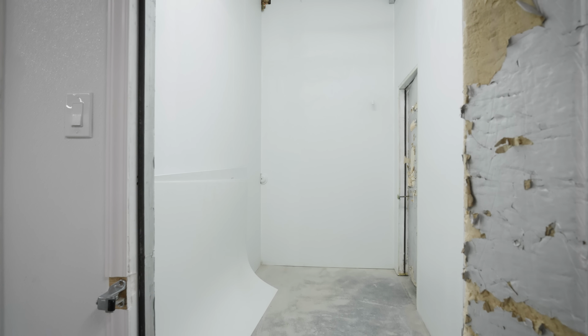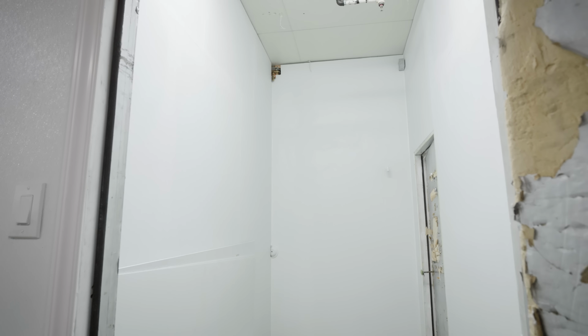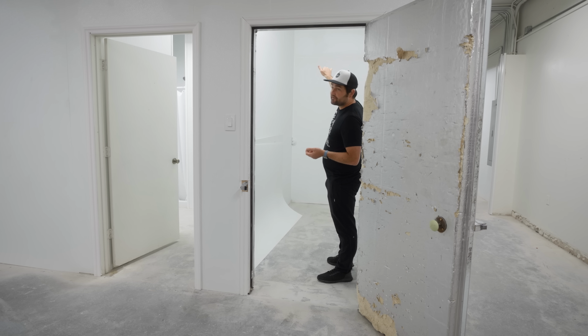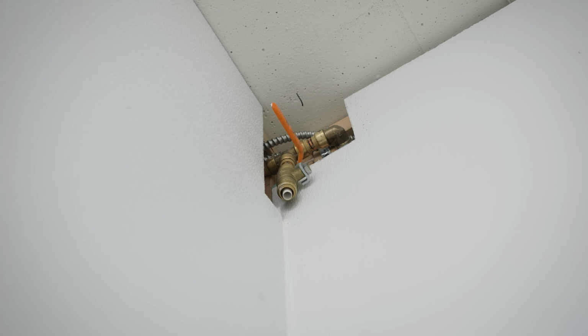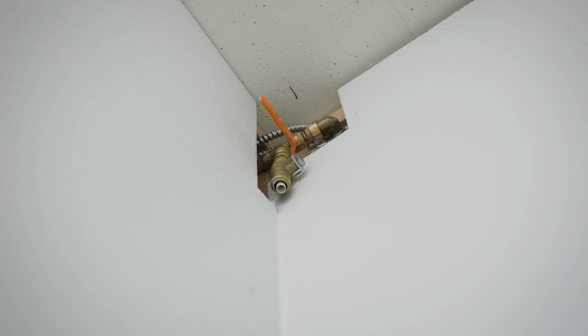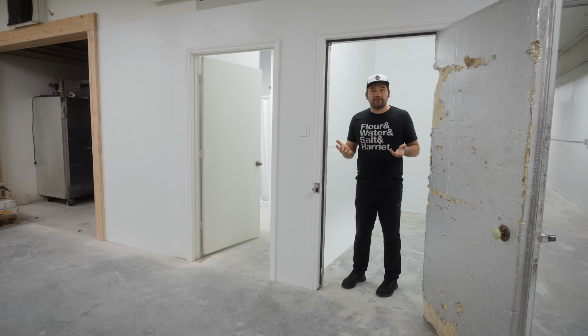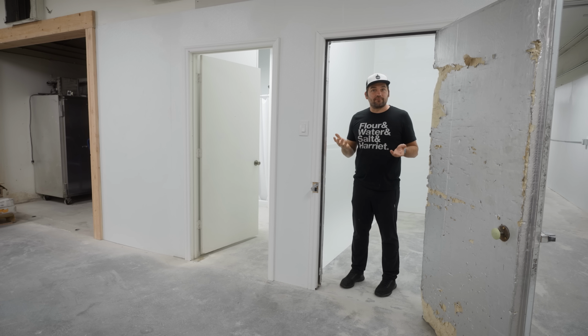And the goal of this room is for it to be 84 degrees and 80% humid. We will hang a freezer coil. It has heaters on the back of it. We'll fashion a pan underneath that freezer coil with a float valve. So there's a water hookup there, there's drain, and there's power in the room ready to go. The heaters are typically in a walk-in freezer used for defrosting the freezer.